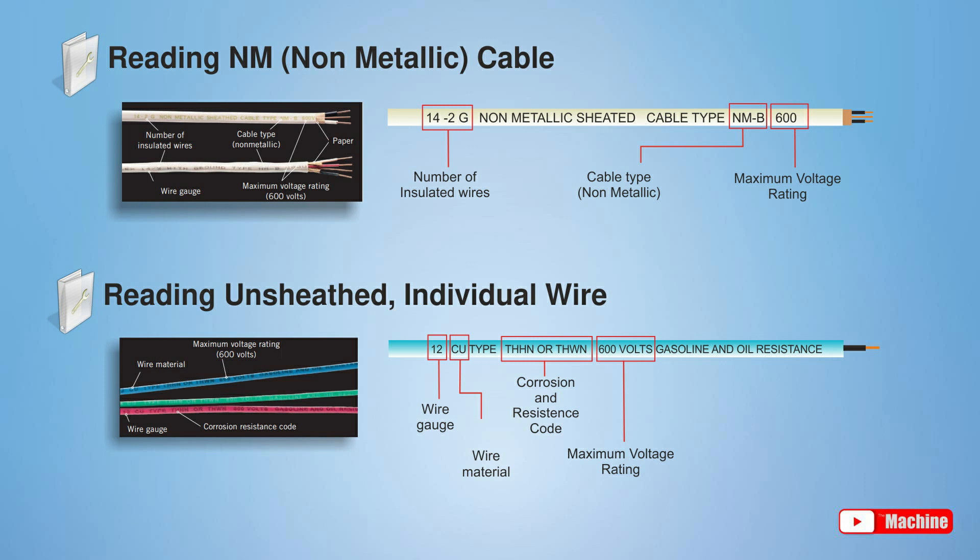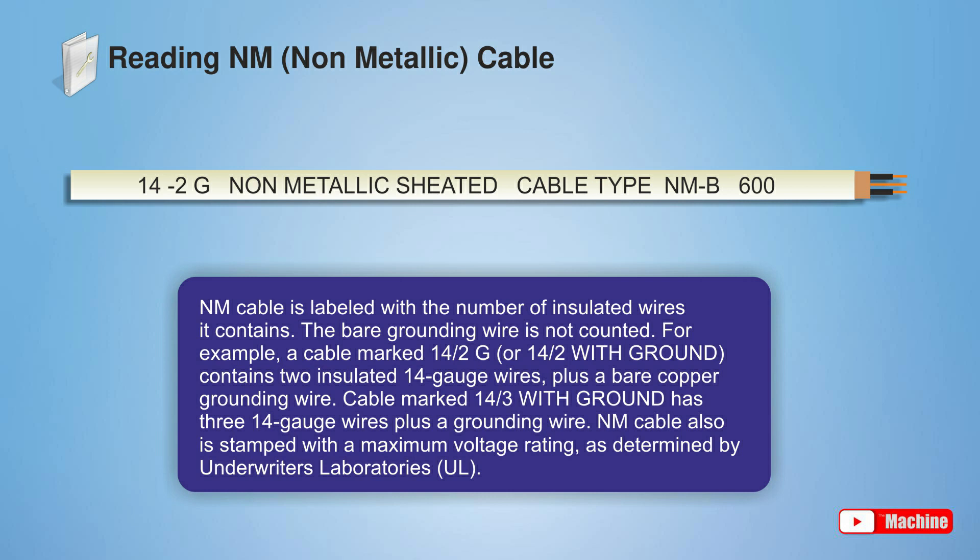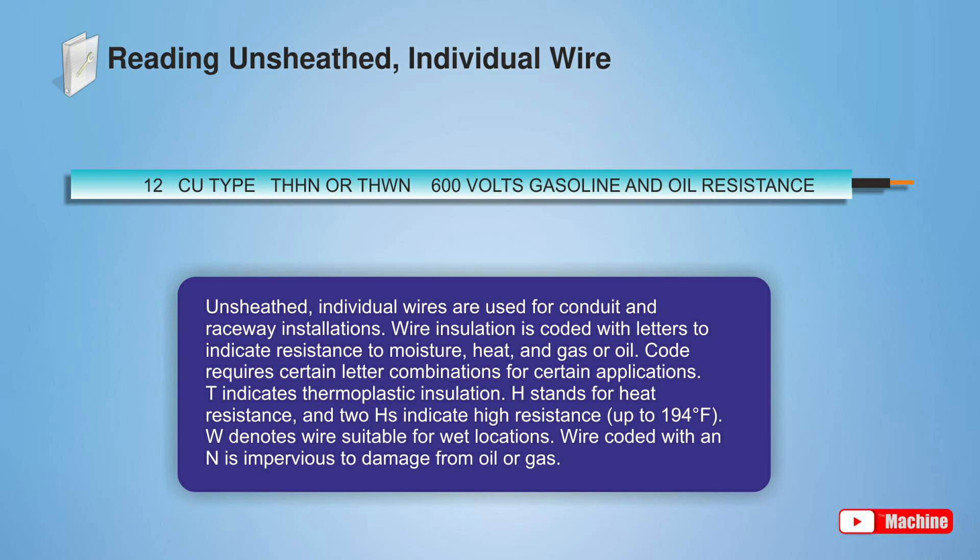Let's take a closer look and check the wire label indication meaning. 14 is the wire gauge, and 2 indicates the number of insulated wires. NM is the cable type, meaning non-metallic. 600V means the maximum voltage rating. For unsheathed wire, 12 means wire gauge. CU is the wire material, meaning copper. THHN, as mentioned before, is the resistance code. And 600V is the maximum voltage rating.